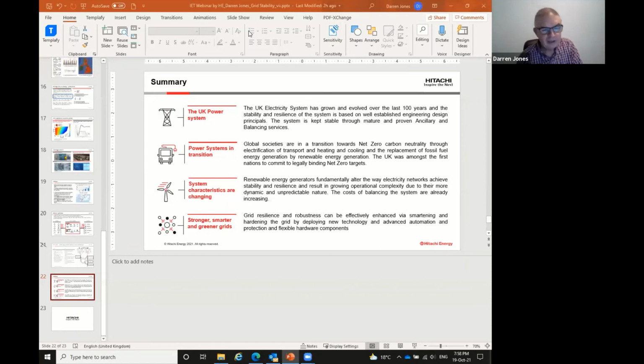That was a similar experience to when, as I mentioned, in 2018 the low frequency demand disconnect schemes kicked in, and the distribution networks were disconnected automatically. They can't then reconnect immediately, because that would cause such a big spike in demand that it would drag the frequency down. So to recover from those low frequency demand disconnect events, the distribution companies have to sectionalize their own networks and bring them back section by section, so you don't get that big shock of demand.